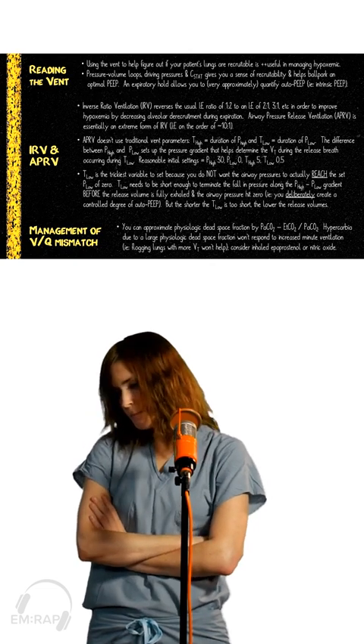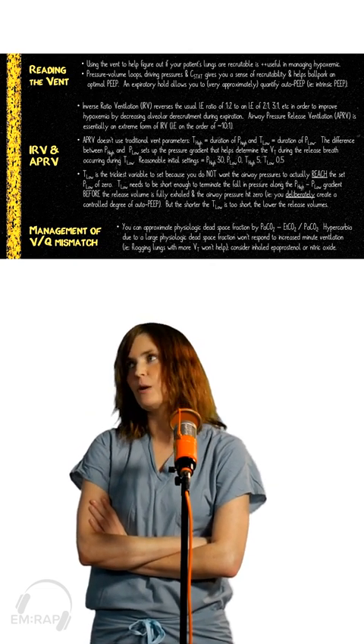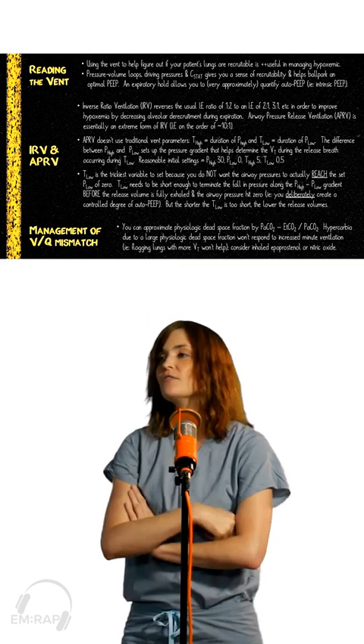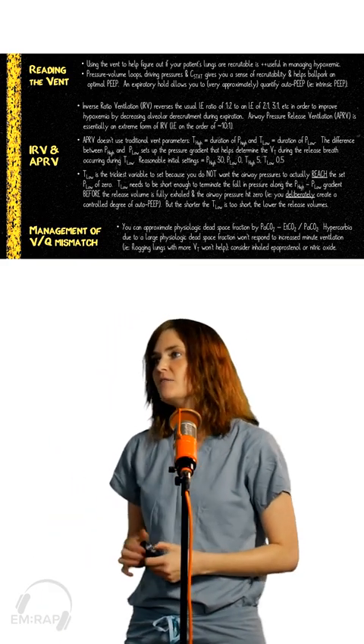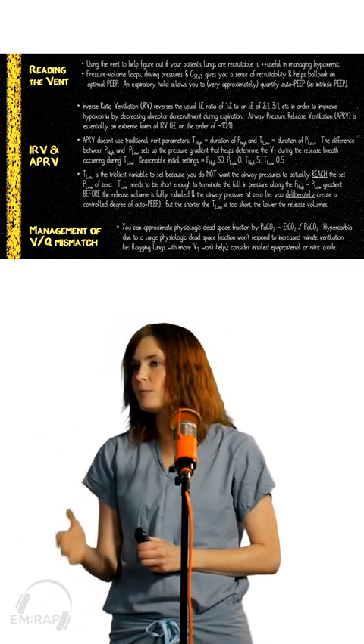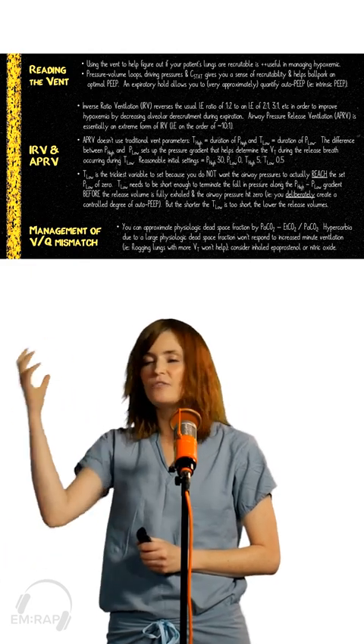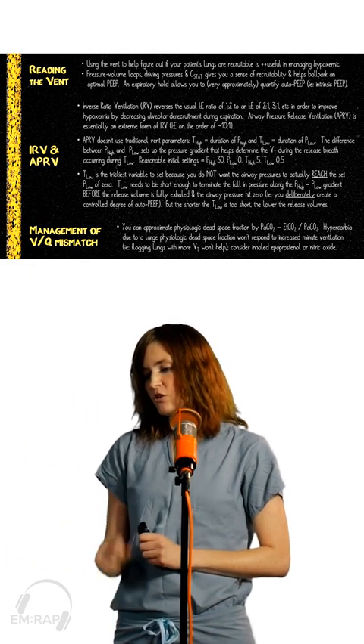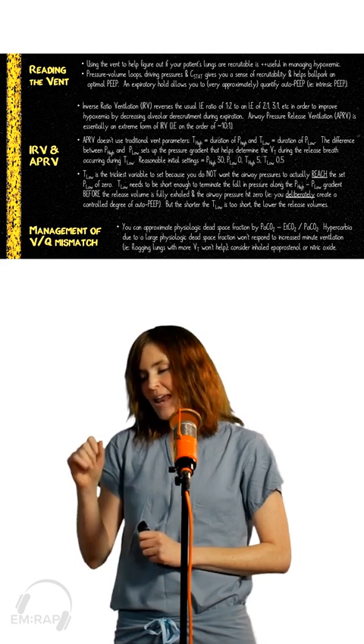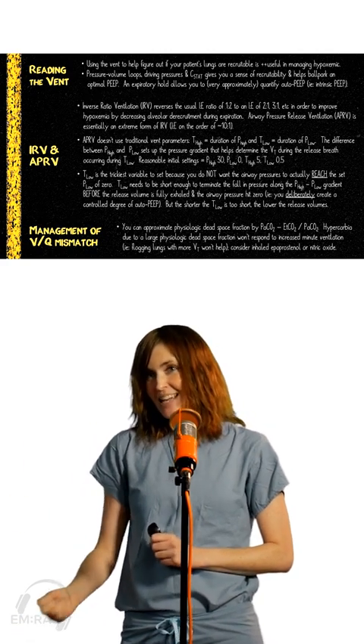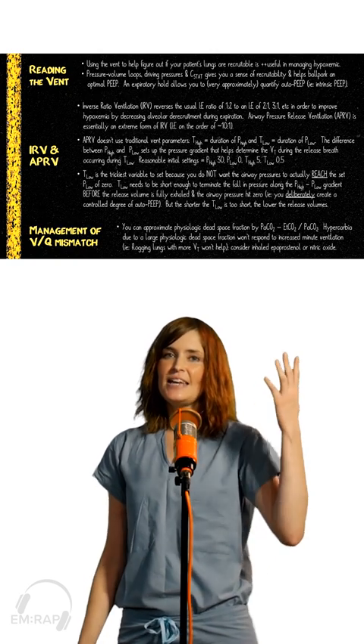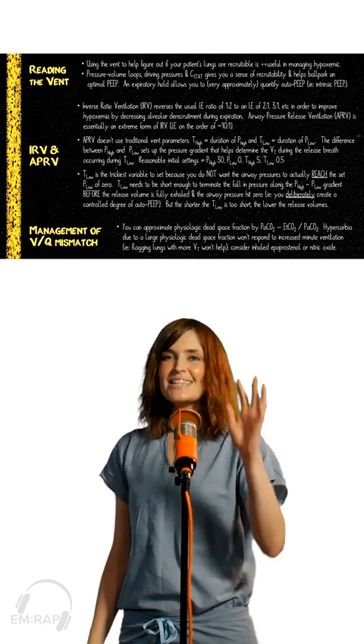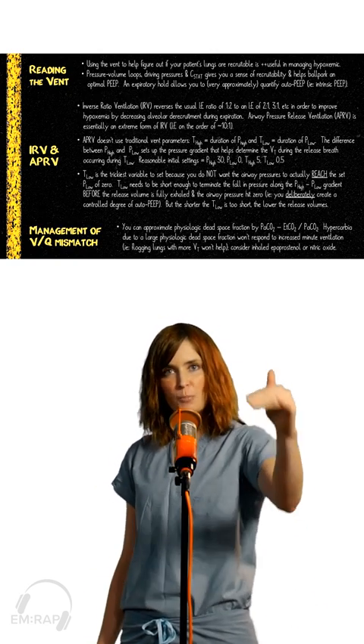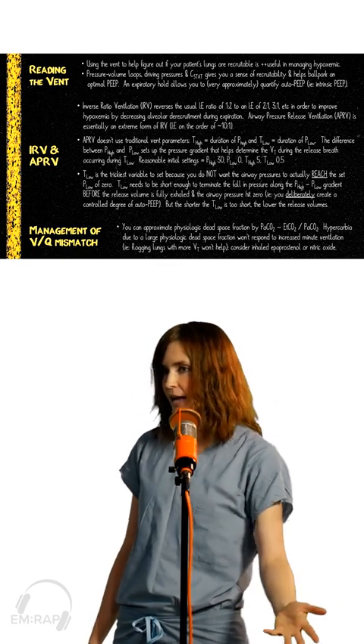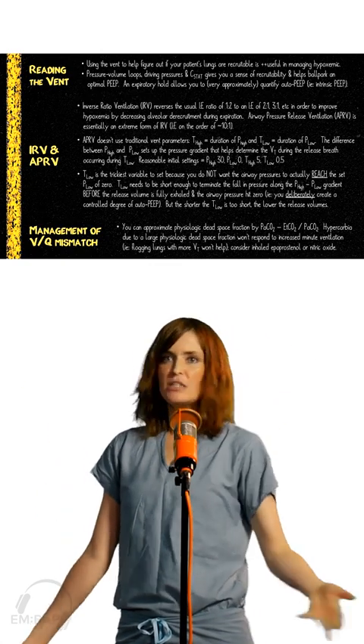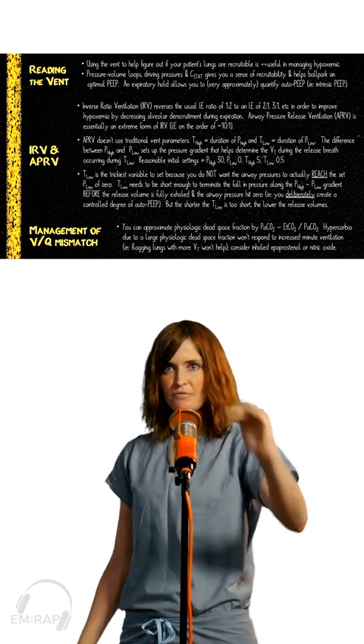So what I started doing, again, as a safety net, if I was at a place where I'm like, I don't know if I can feel really good that I'm going to give this patient the attention they need, I don't have time, I don't have cognitive offloading sufficient to do it. What I started doing is not setting the P-low at zero, because that makes it not exactly foolproof, but it's a safety net. Because that way, if your P-low is set at 5, you can't get to 0, right? Because the hill stops at 5.